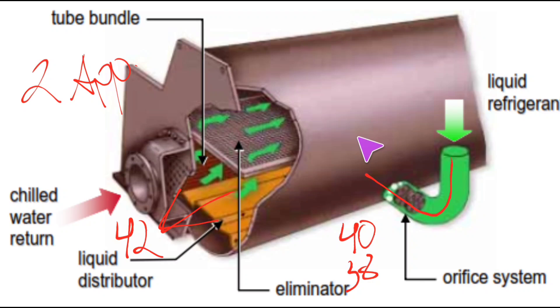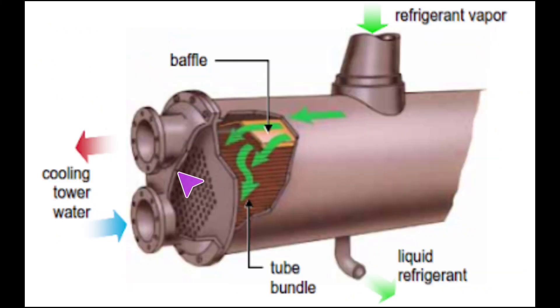This is an example of a Trane condenser. We got discharge gas coming in, liquid refrigerant going out. Whenever the condenser water is real dirty or maybe you've got a GPM issue come in and out, it's going to affect it. But let's say we had a leaving condenser water of 80 degrees. Well, we got to be above it, so our saturation on the barrel is going to be, let's say, 81. Okay, that's going to give us a one degree approach on that condenser barrel, and this is for a centrifugal design.